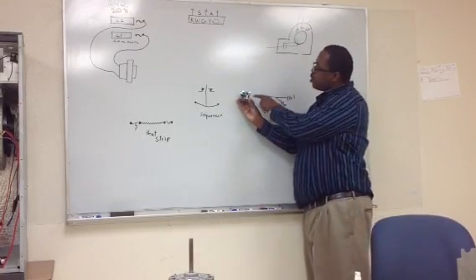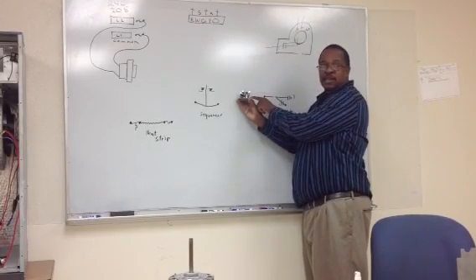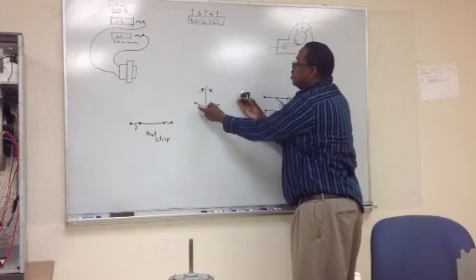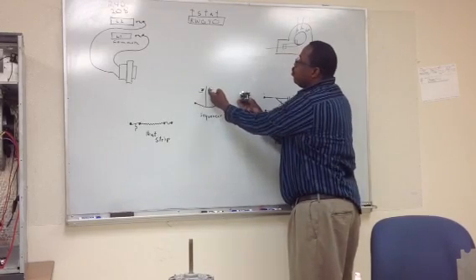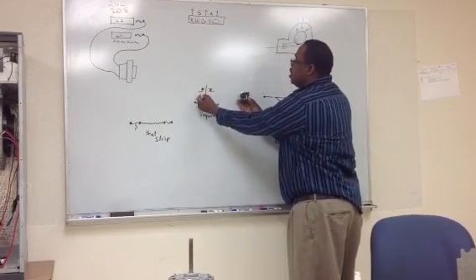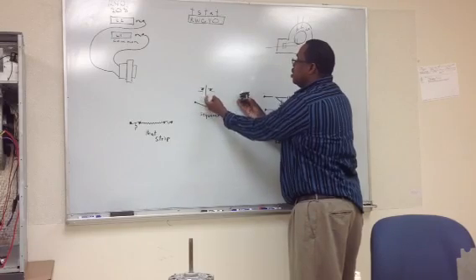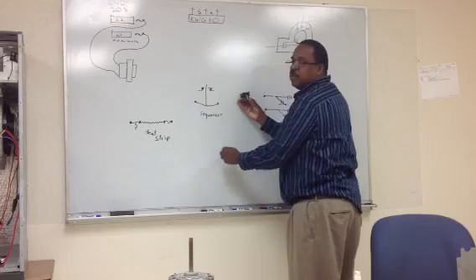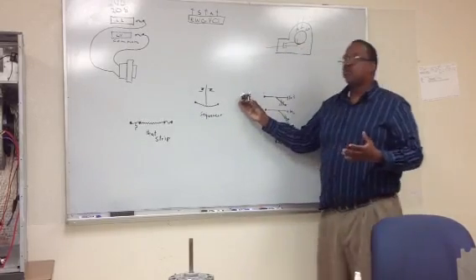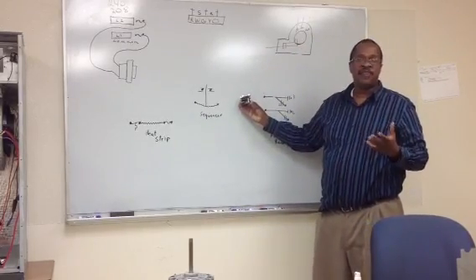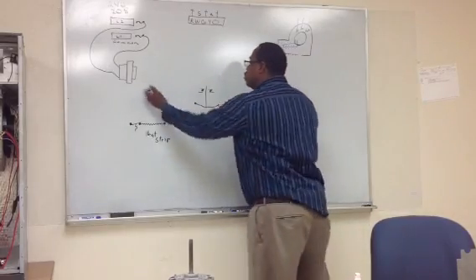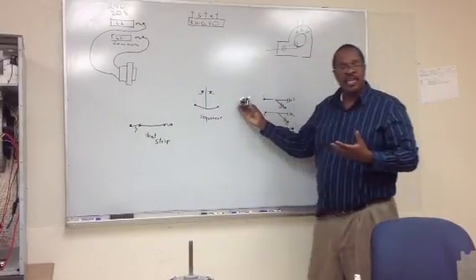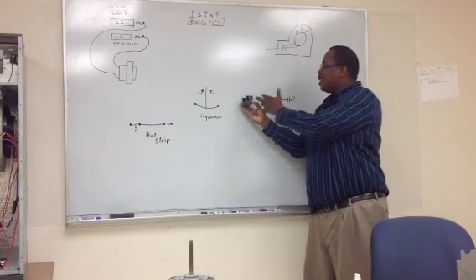But this sequencer got one circuit up top, and it has another circuit in the middle. And then at the bottom, it has another circuit. Well, the low voltage is always at the bottom. And then I only put one circuit on this for this drawing, but it could have another one. So each one of these circuits can control a different heat strip. Now one thing about the sequencer, it is a time-delayed device. It consumes 24 volts at the bottom. And as it generates heat, it slowly moves and closes the contacts in the sequencer.